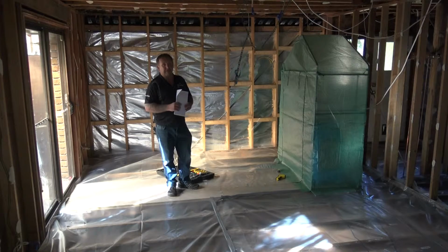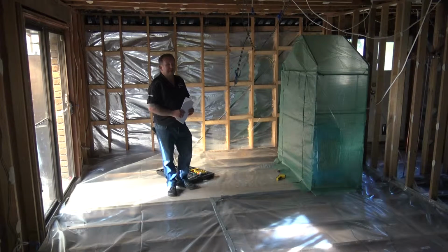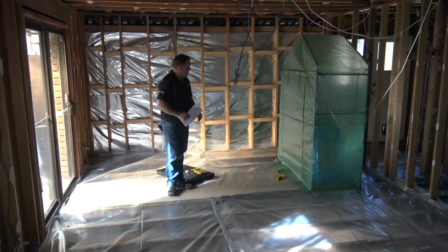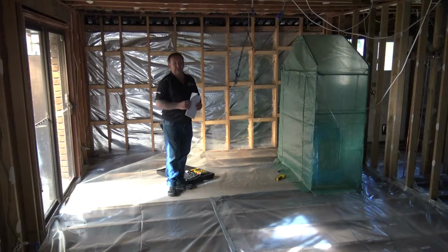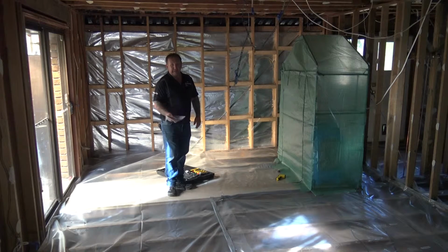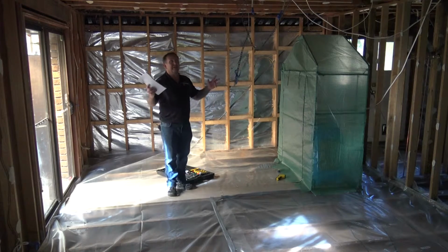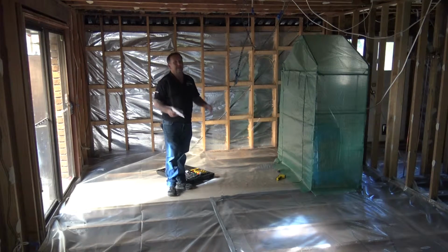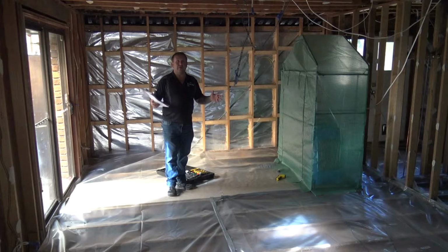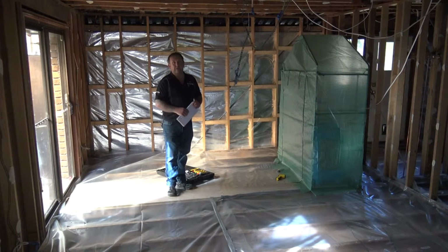So we're getting a much greater evaporation potential. So we're getting some really good results here, and it's something that with a traditional dehumidifier and a fan in this situation, it'd just take too long and it just wouldn't be efficient. But this is a super quick way of getting it dry by concentrating it on that one area where it's needed. So it's not needed everywhere else, everything else is all right. So there's no point in trying to dry the whole building, especially in those conditions. This is the way to concentrate it and target that area that we want to dry.